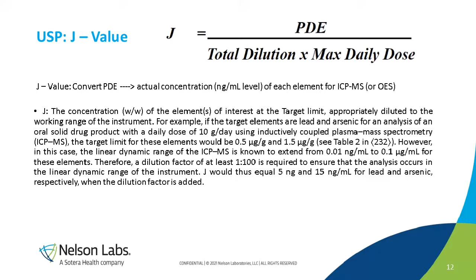Now, the definition of J is the concentration of the element of interest at the target limit, appropriately diluted to the working range of the instrument. Since we are talking about ICP-MS, we know that ICP-MS is a very sensitive instrument. It could go down to the nanogram per milliliter level, even to the picogram per milliliter level. So obviously, if you use the microgram per milliliter level, it will destroy the instrument, or I should say saturate it with all these elements, so you cannot use it next time. So we need to properly dilute into the working condition. That's where this J value comes up.